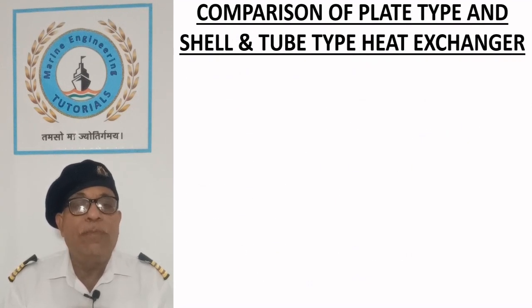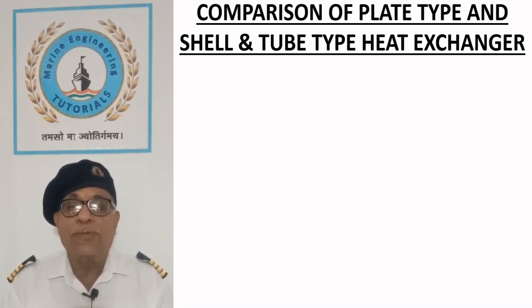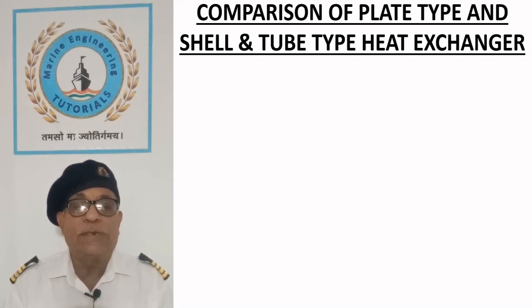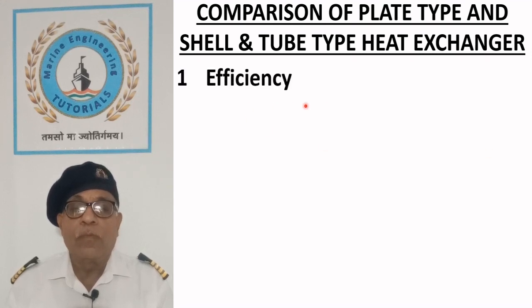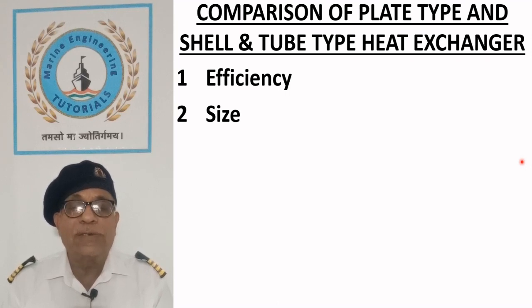Comparison of plate type and shell and tube type heat exchanger. We will compare the two types of heat exchangers on the following basis. Efficiency. The major advantage of plate type coolers over the tube type coolers is their higher efficiency. Size. Higher efficiency of the plate type coolers is reflected in a smaller size as compared to shell and tube type coolers for the same cooling capacity.